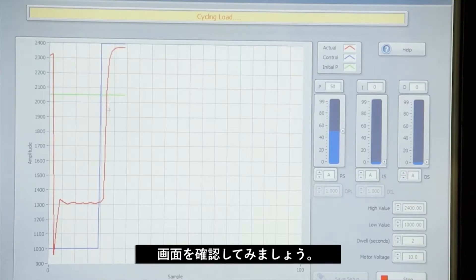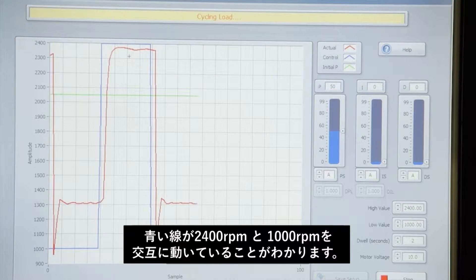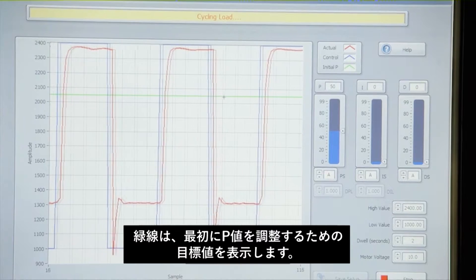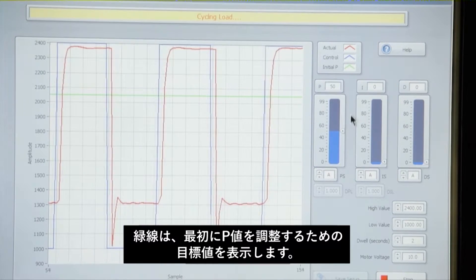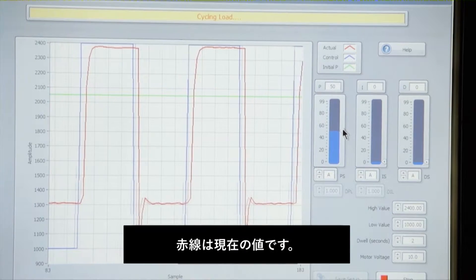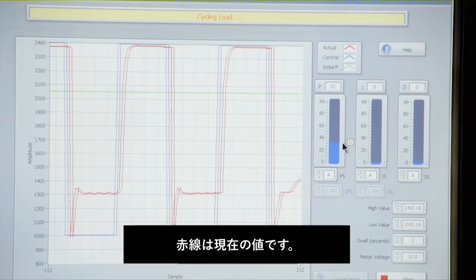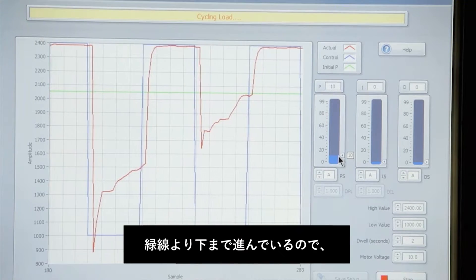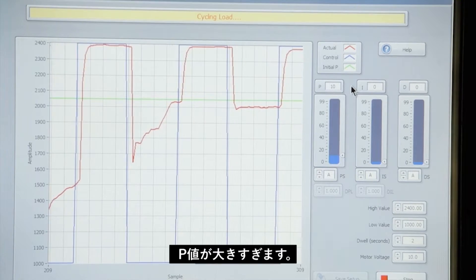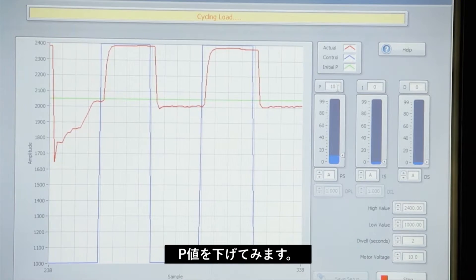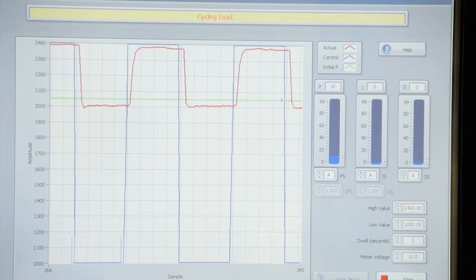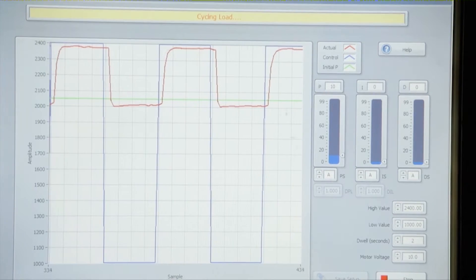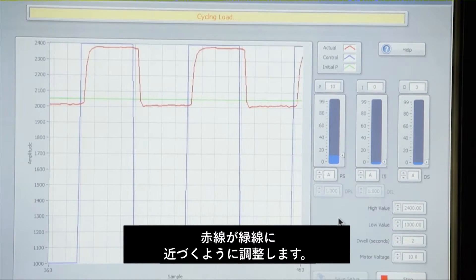Now what is happening here is our blue line is cycling between 2,400 and 1,000 rpm. Our green line is showing the initial set point for the P term, and the red line is showing our system response. You can see that the red line is coming well down below the green line, so our initial gain setting is too great and we need to lower this until we get the red line fairly close to the green line.